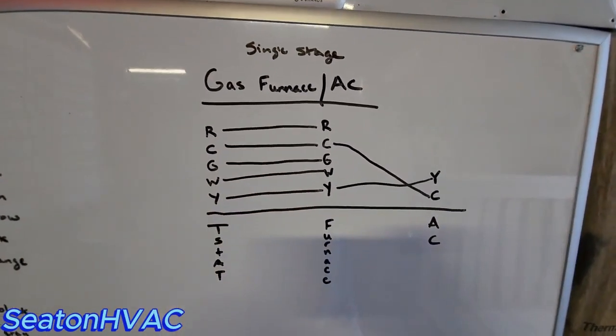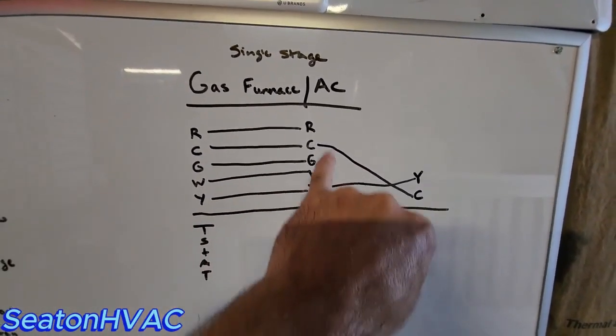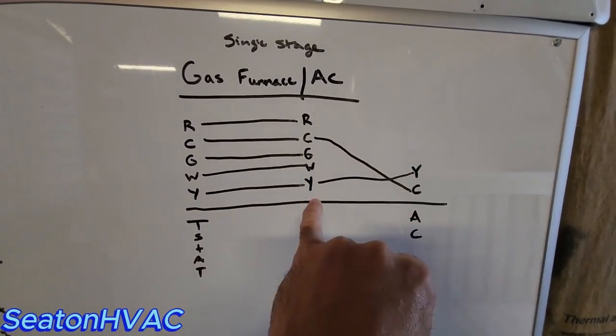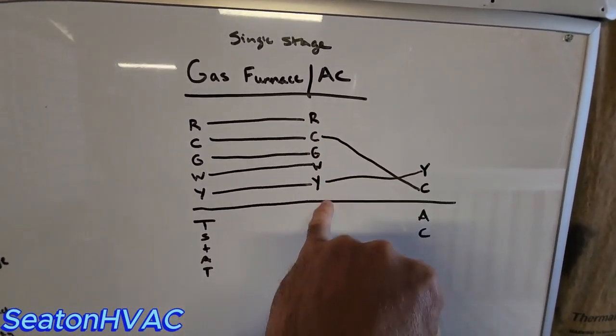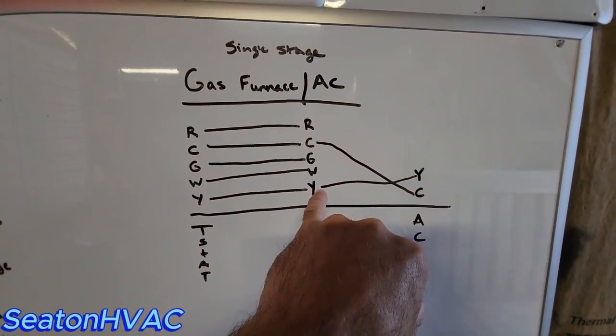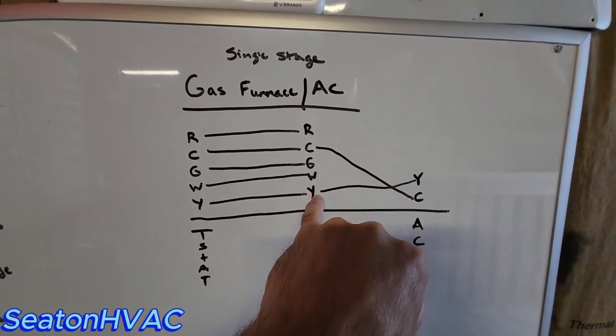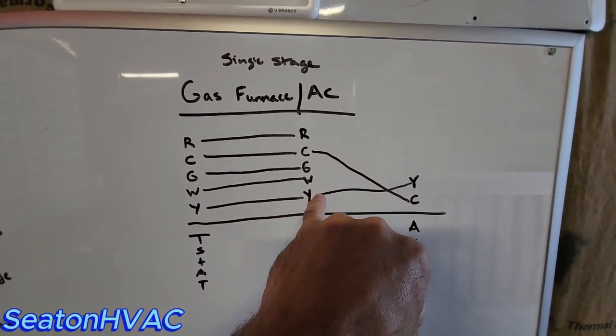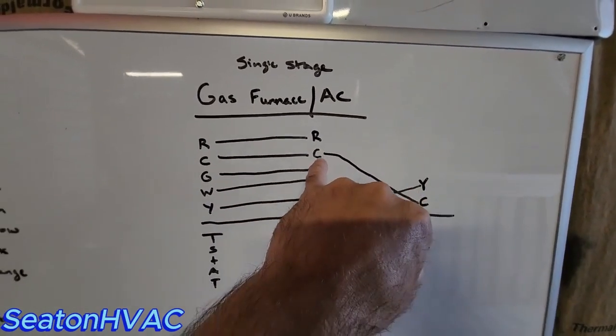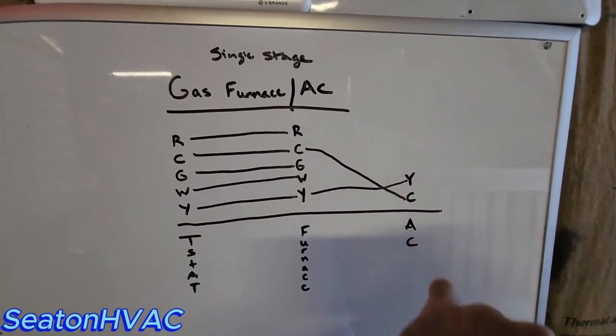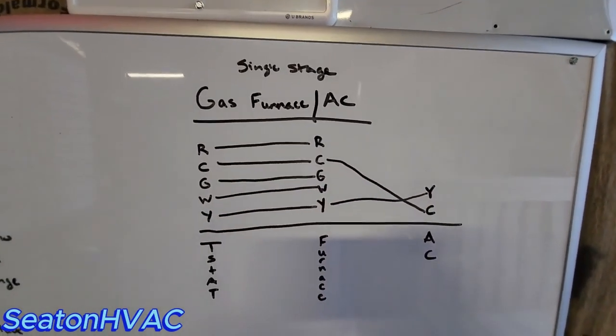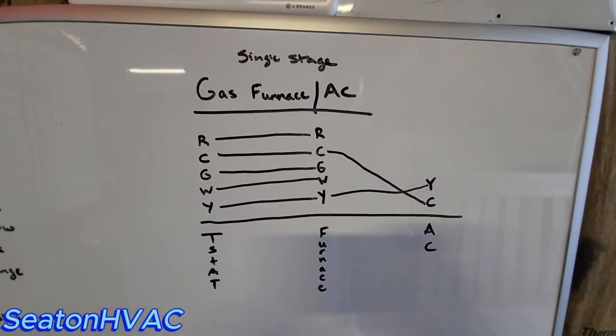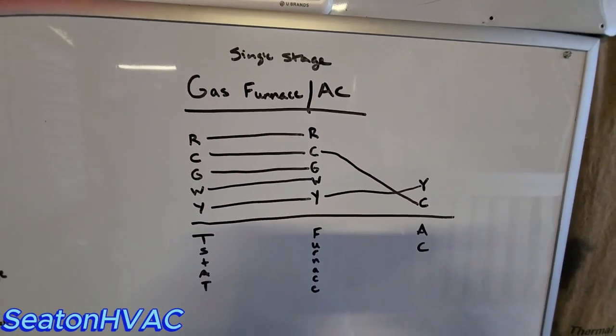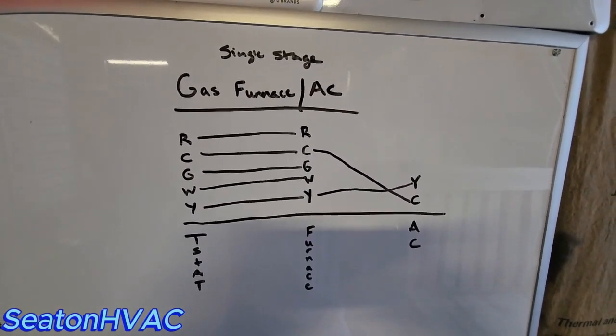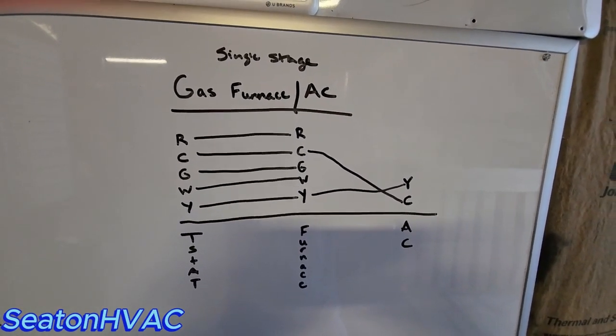Real simple, real easy. And then from your gas furnace out to your single stage air conditioner, it's your first stage compressor wire is what I call it. Y, yellow, outside. And then you'll do your blue, which is your common outside. That's all you do. Simple single stage gas furnace AC. Let's go over a two-stage gas furnace with a two-stage AC.